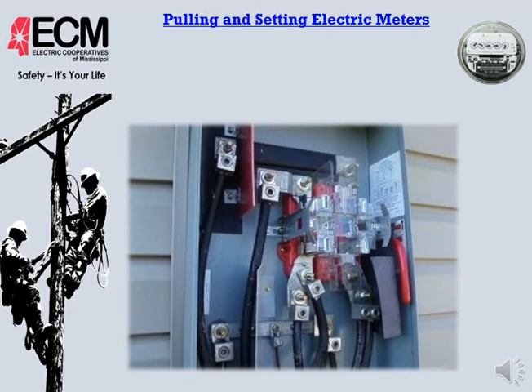On this photo, we've got a 320 amp meter base on a house, and this one has a bypass handle. We all know how these bypass handles work - we raise the handle to bypass the meter base on the inside behind the meter so we can pull the meter without interruption of power. On this one, the handle has been bent so the bypass was actually pushed up into the bypass position, and then the handle was bent down so it would look like the bypass was open instead of closed. This is something we really need to be looking at closely.